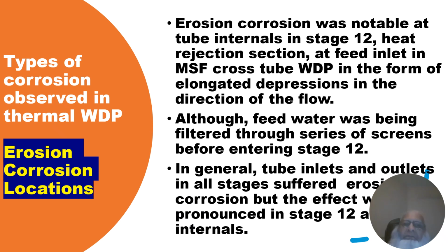In general, tube inlets and outlets in all stages suffered erosion corrosion, but the effect was more pronounced in stage 12 tube internals.